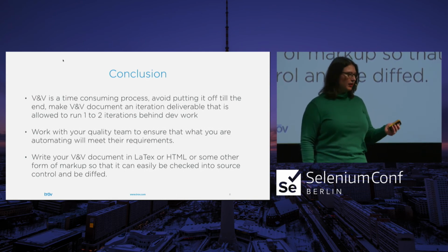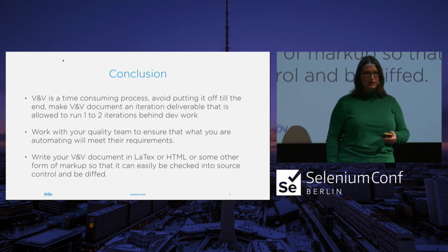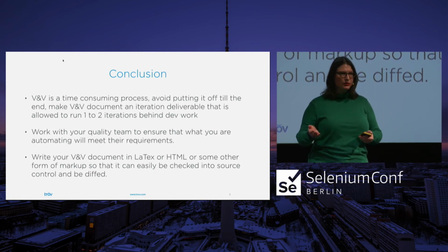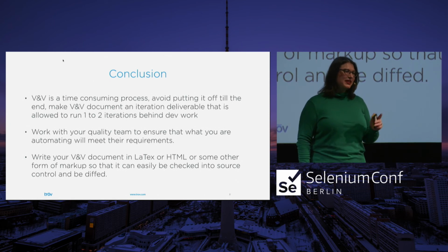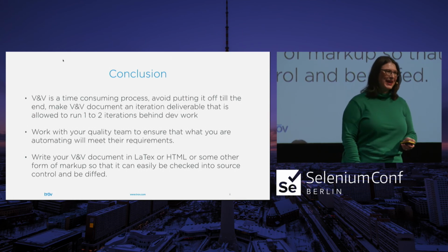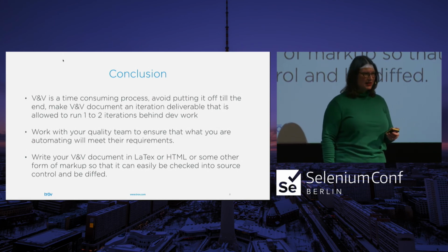So if you plan to do something in an automated fashion, you want to make sure you have them on board. Because if they see it late in the process and they say, all these automated tests, we can't validate the tools that you used, so there's also a process of tool validation. So any tool that you use has to be validated, right? So the language you wrote the software in, interestingly enough, they do not require that to be validated. But your automated testing tool, yes, they would like that to be validated. So the language doesn't have to be validated because it's complicated, but mostly because you're validating the software that you wrote with it. So you kind of get to skip that process.